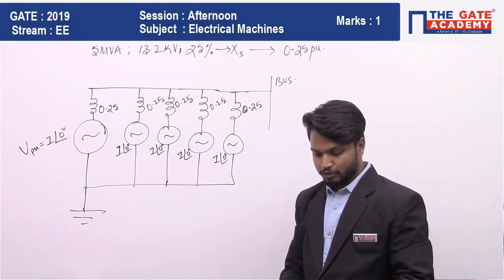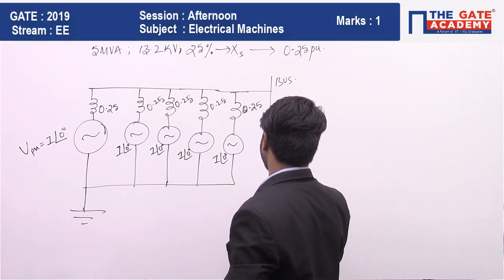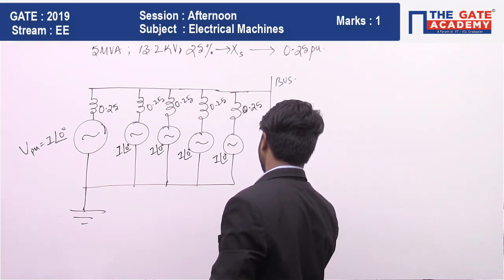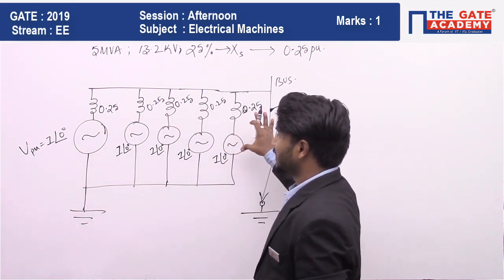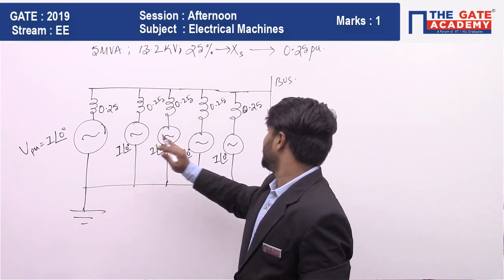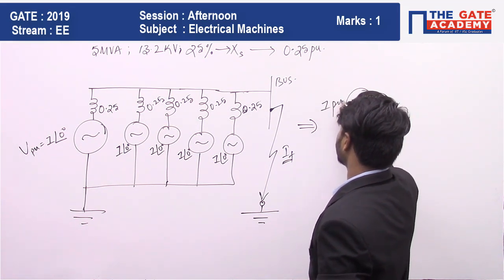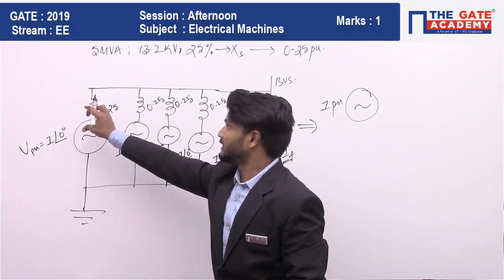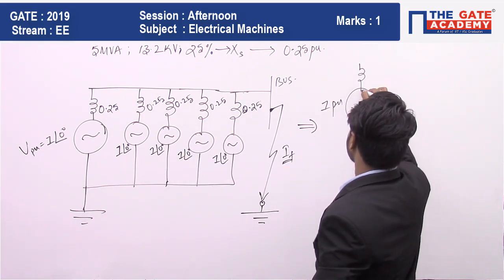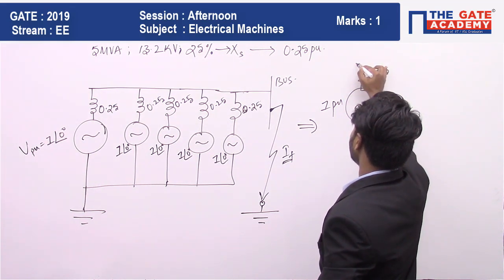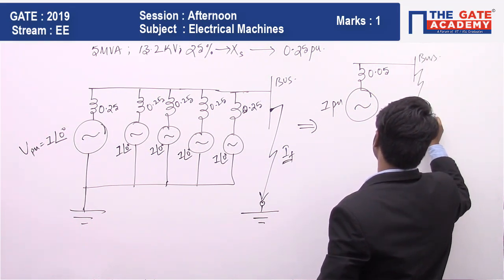The question asks for the short circuit level in MVA at the bus bar. If a short circuit fault occurs at the bus bar between the ground and the bus bar, what is the fault level? Since all five voltages are the same, they can be replaced by a single voltage source of one per unit, with five reactances in parallel: 0.25 divided by 5 gives 0.05 per unit.